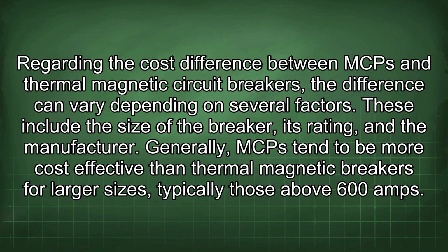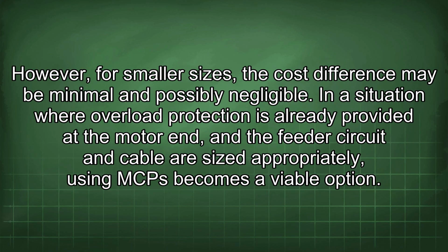Regarding the cost difference between MCP and thermal magnetic circuit breakers, the difference can vary depending on several factors. These include the size of the breaker, its rating, and the manufacturer. Generally, MCP tend to be more cost-effective than thermal magnetic breakers for larger sizes, typically those above 600 amps. However, for smaller sizes, the cost difference may be minimal and possibly negligible.